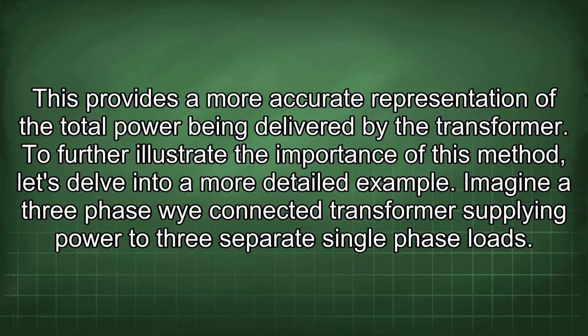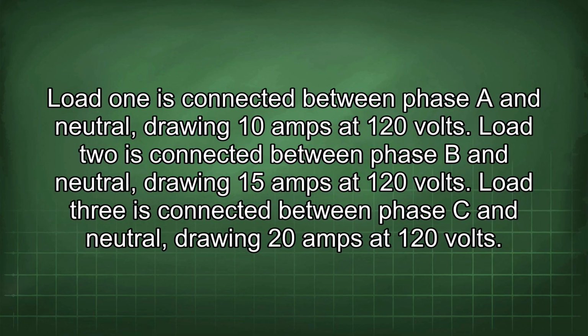To further illustrate the importance of this method, let's delve into a more detailed example. Imagine a three-phase Y-connected transformer supplying power to three separate single-phase loads. Load 1 is connected between phase A and neutral, drawing 10 amps at 120 volts. Load 2 is connected between phase B and neutral, drawing 15 amps at 120 volts. Load 3 is connected between phase C and neutral, drawing 20 amps at 120 volts.